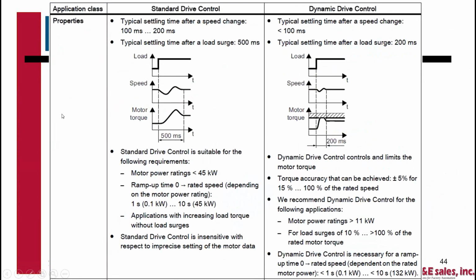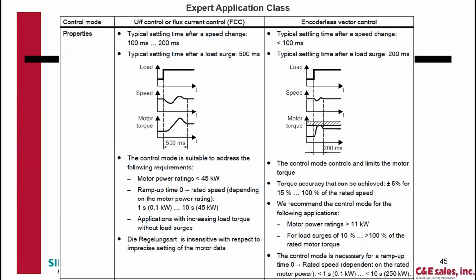With standard or dynamic, you're going to preset some of these parameters, which makes it a little easier. Or you can do expert, where you've got different control modes. Here you see volts per hertz on the left, which looks very much like standard, while encoderless vector is more like what dynamic is going to be. It just depends on how you want to set it up. Expert does give you more choices, but you really have to know more about what you're doing to pick and choose those.